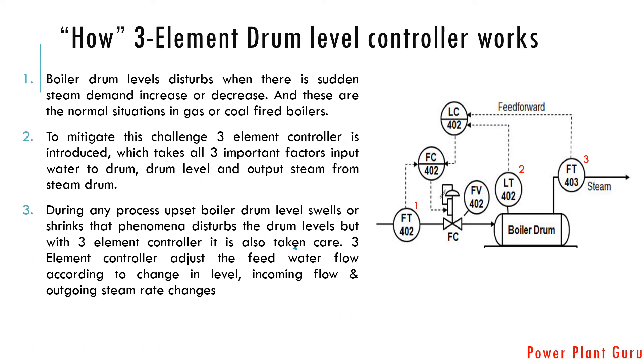The swelling effect increases the drum level to a certain extent. This time, the swelling that leads to a drum level high is also taken care of by three-element control. At the same time, steam demand has also increased, so the steam drum level controller processes both pieces of information and calculates a revised set point for the feed water control valve, so that the feed water control valve takes action to supply more feed water to cater for the increased steam demand, irrespective of the local phenomenon of drum swelling.